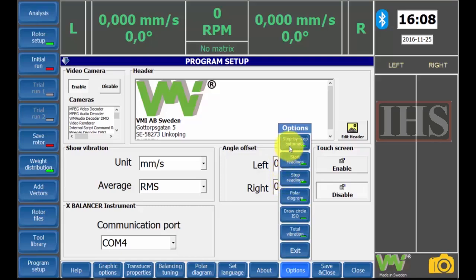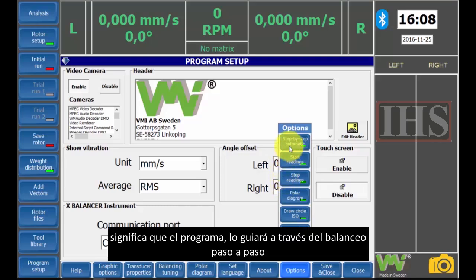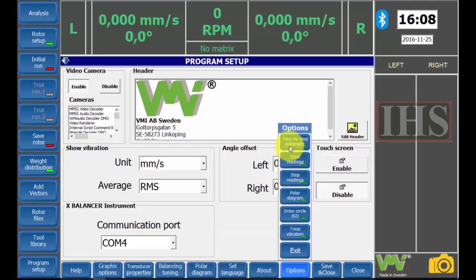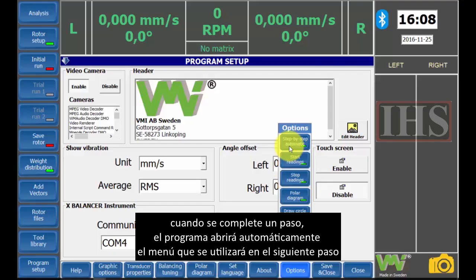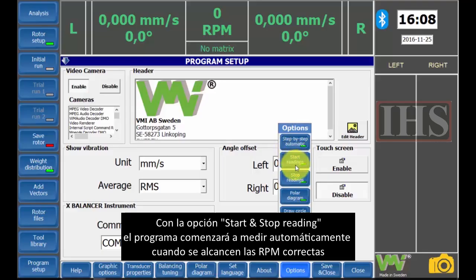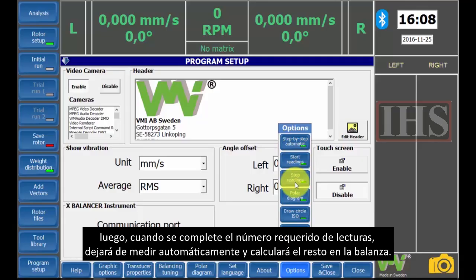Step-by-step option means that the program will guide you through the balancing step by step. When one step is completed, the program will automatically open the menu that shall be used in the next step. With Start and Stop Reading selected, the program will automatically start measuring when the correct RPM is reached. Then, when the required number of readings has been performed, it automatically stops measuring and calculates the remaining unbalance.